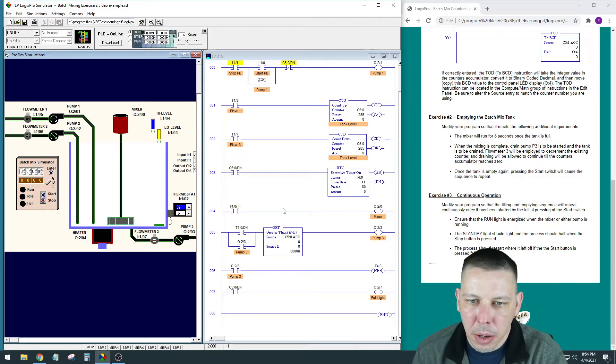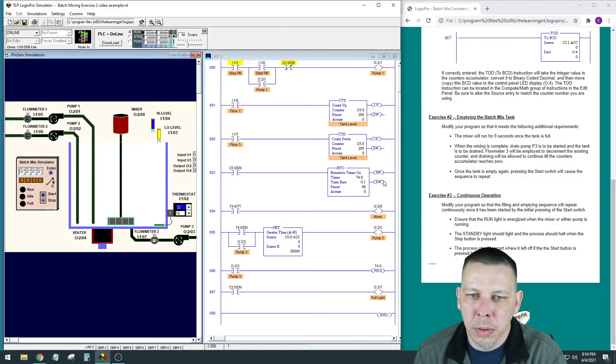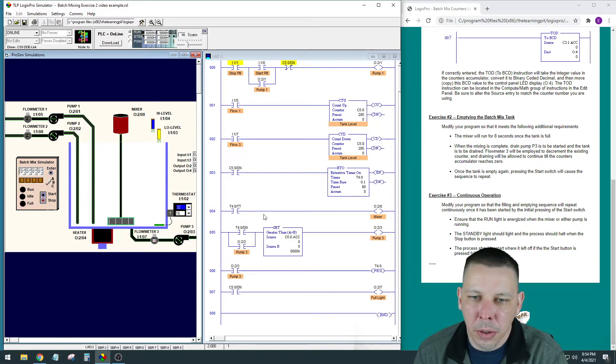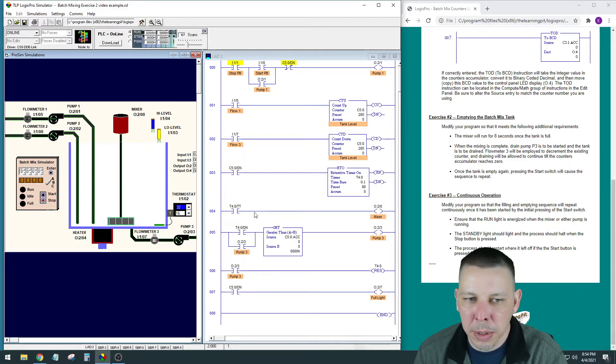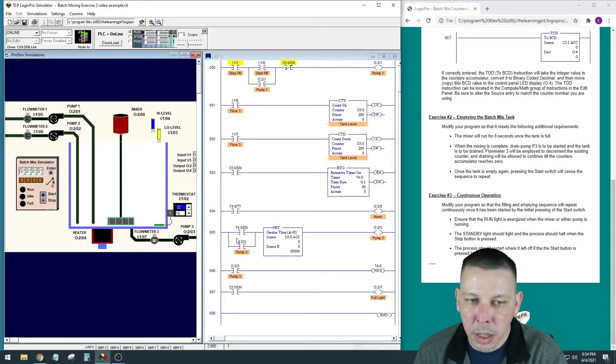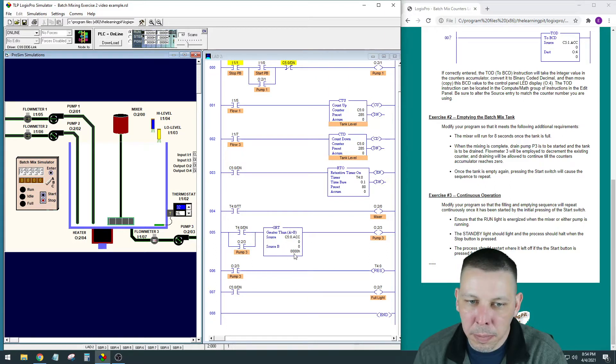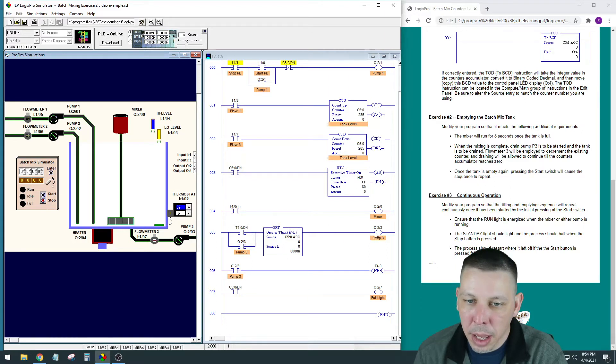So when T4.0 is done, right here when our done bit gets made, it'll execute the next line which would be T4.0 timer timing, which is not made anymore, so the mixer would stop. It would go down here—T4.0 done would allow power through it and our accumulated would be greater than zero because our tank would be full at that point, and pump 3 would start.